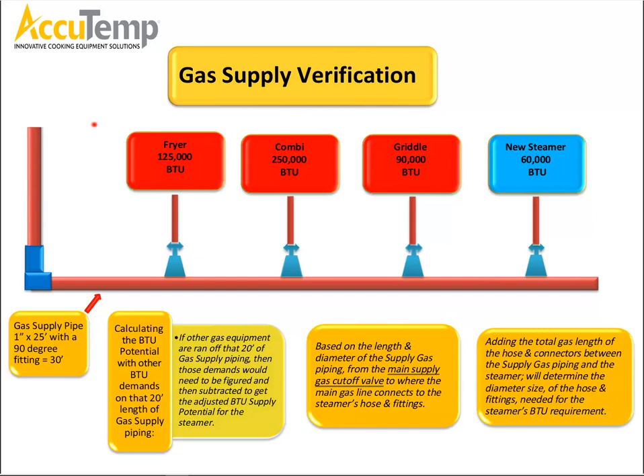Now, going back, remember that 1-inch pipe at 30 feet can only support 377,000 BTUs. So just between the fryer and combi, we're looking at 375,000 BTUs. So based on this map, at this point that 1-inch line cannot support the griddle, and it can definitely not support that steamer at 60,000 BTUs. So as they're building this restaurant, they would have to either split the load or install a larger diameter pipe to be able to support the necessary BTUs.